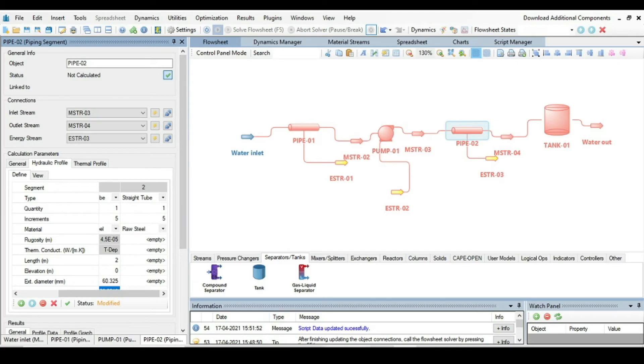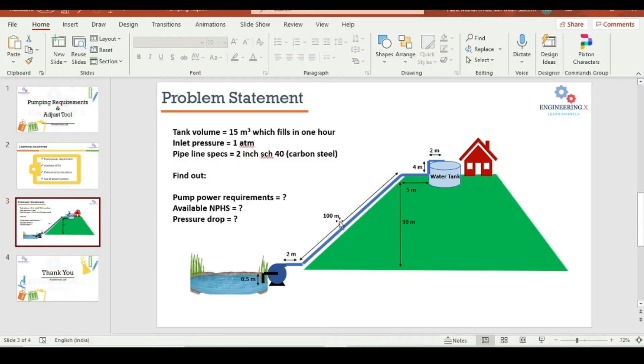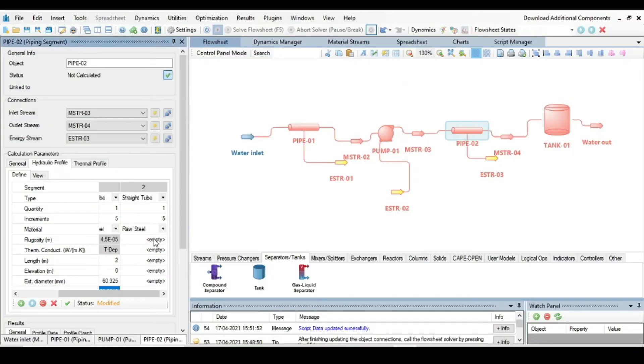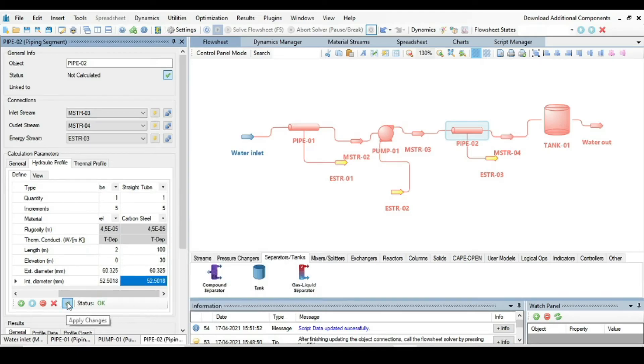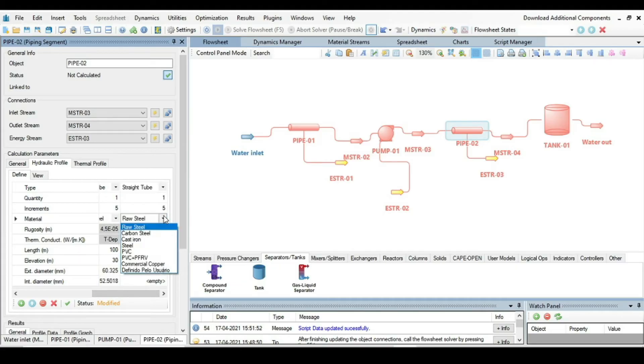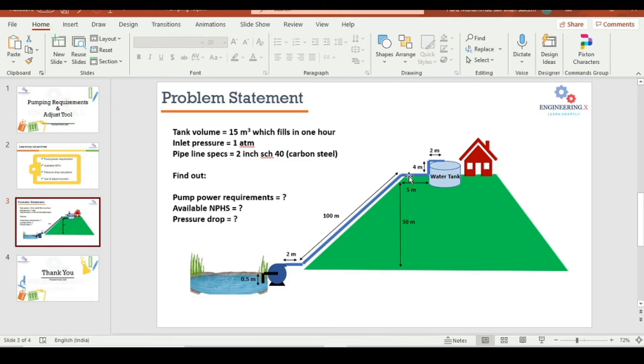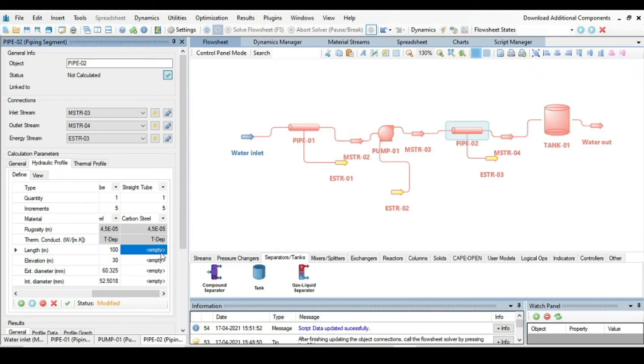The second segment is 100 meters in length with an elevation of 30 meters, carbon steel, two-inch schedule 40. Accept the changes. Add a third segment: carbon steel, 5 meters long and horizontal, so length is 5 meters and elevation is 0, two-inch schedule 40. Apply changes.